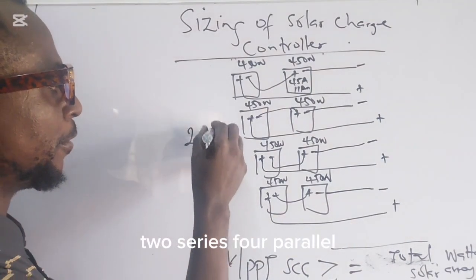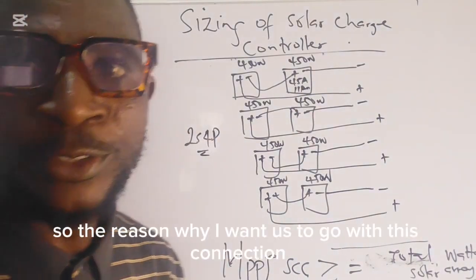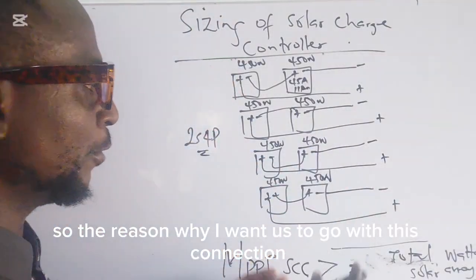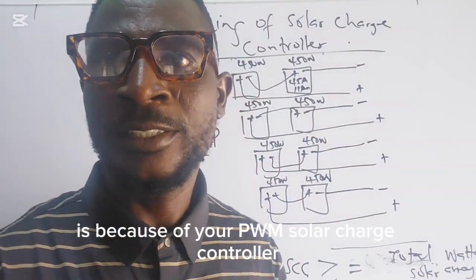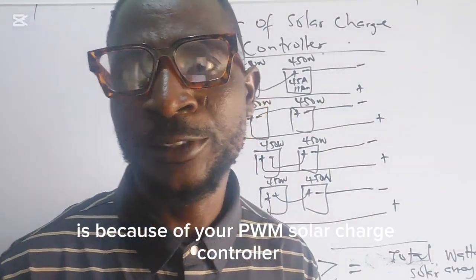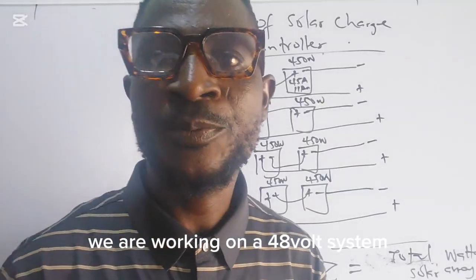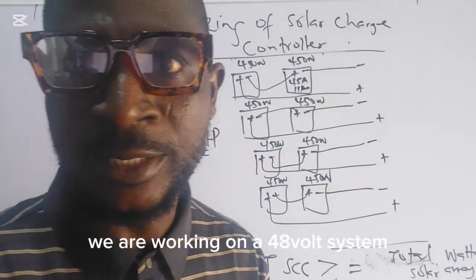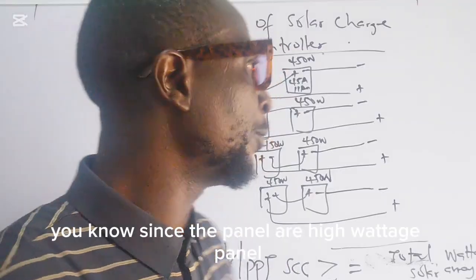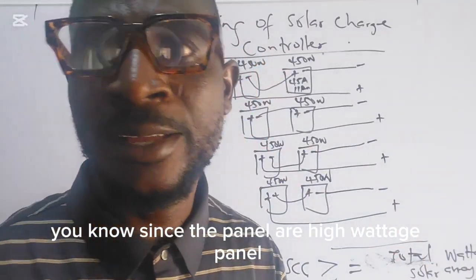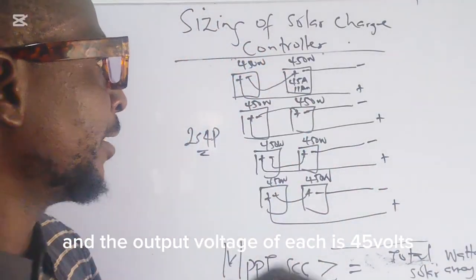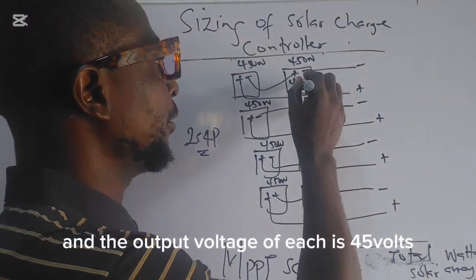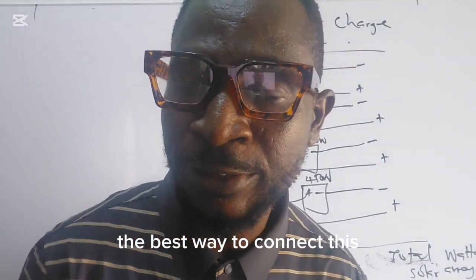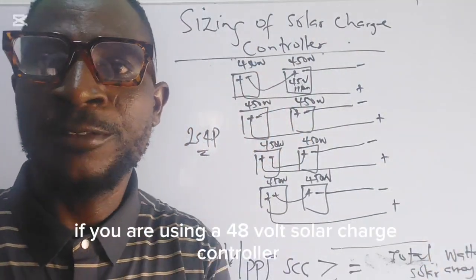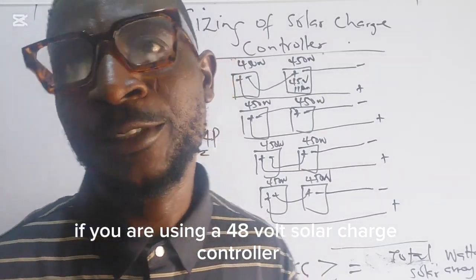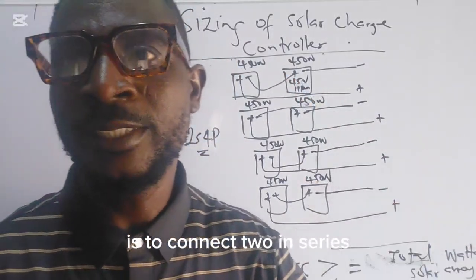2 series, 4 parallel. The reason why I want us to go with this connection is because of your PWM solar charge controller. We are working on a 48 volt system. Since the panels are high wattage panels and the open circuit voltage of each is 45 volts, the best way to connect this, if you are using a 48 volt solar charge controller, is to connect 2 in series.